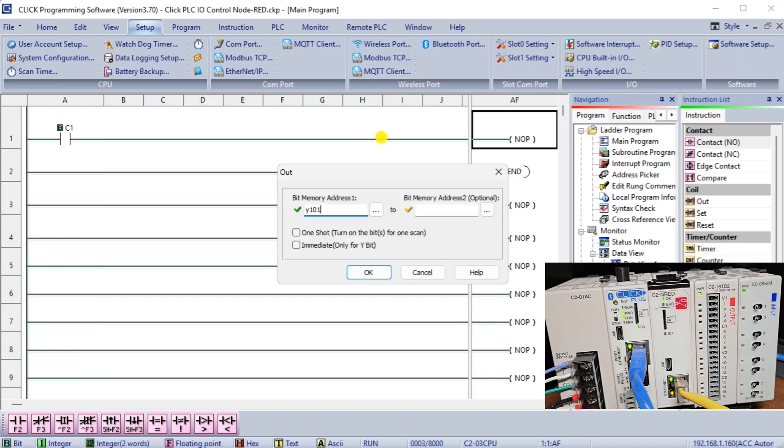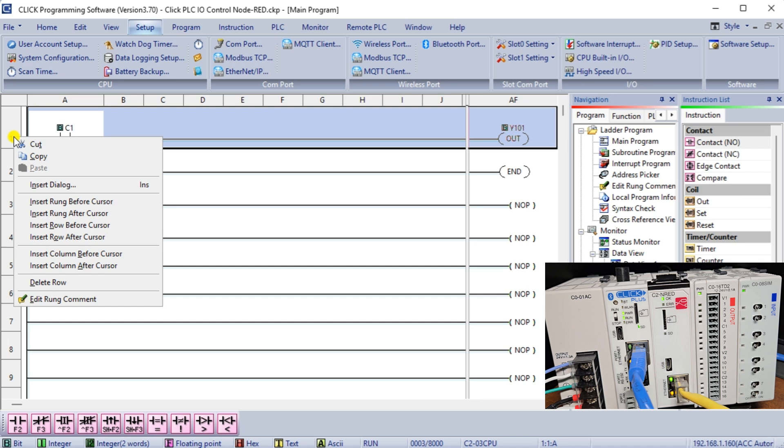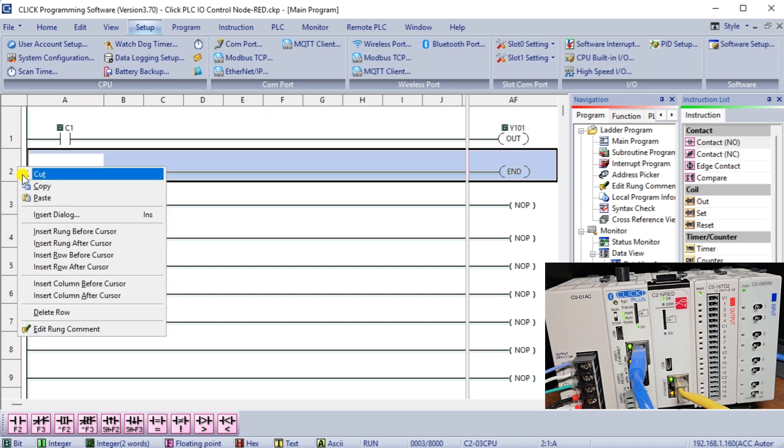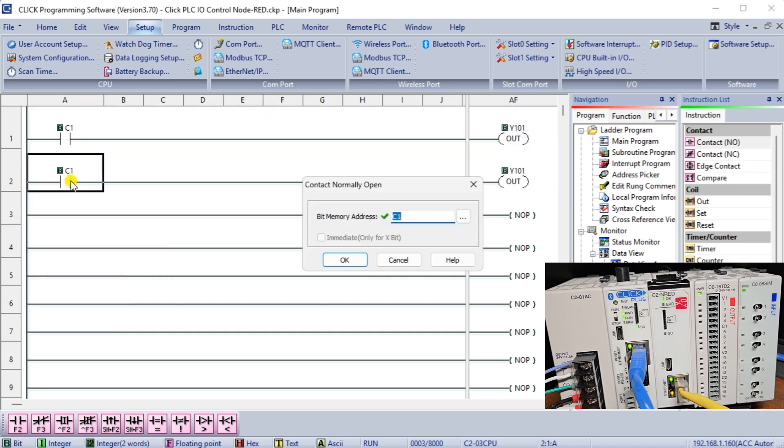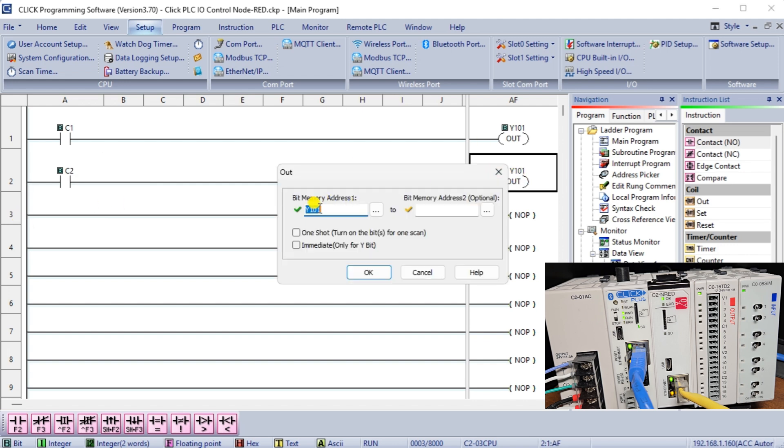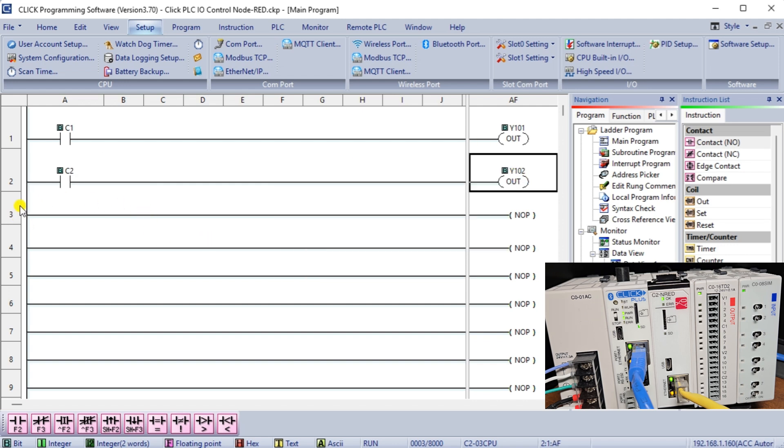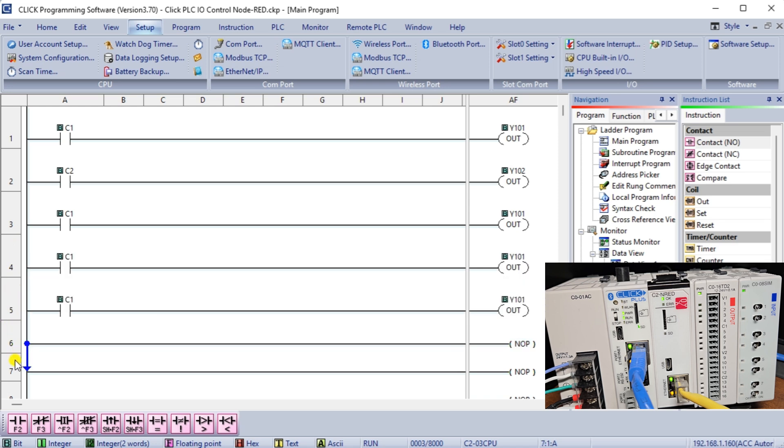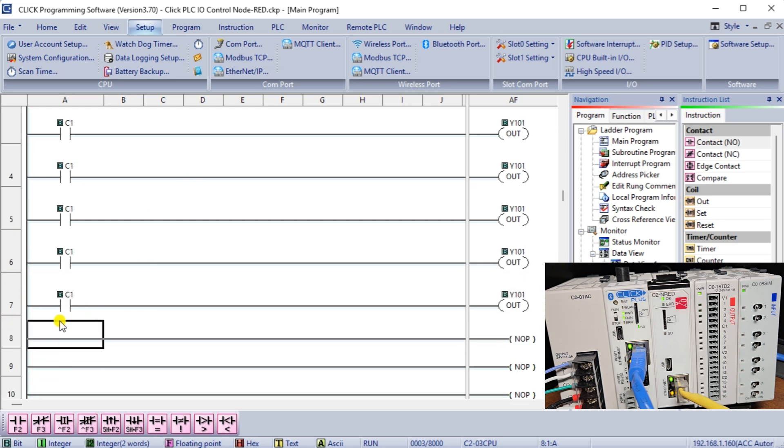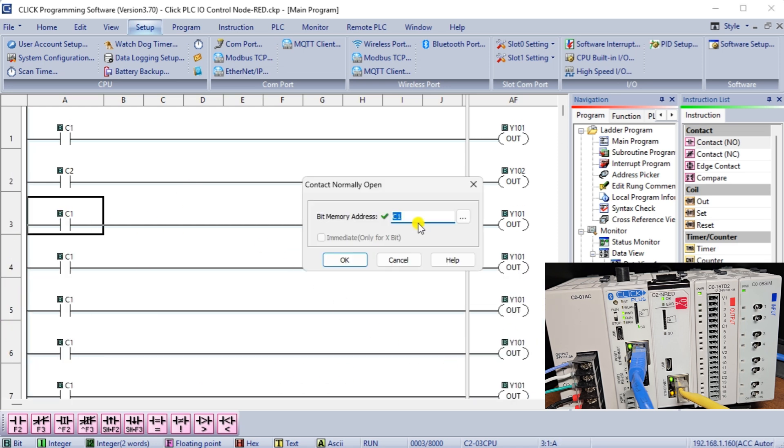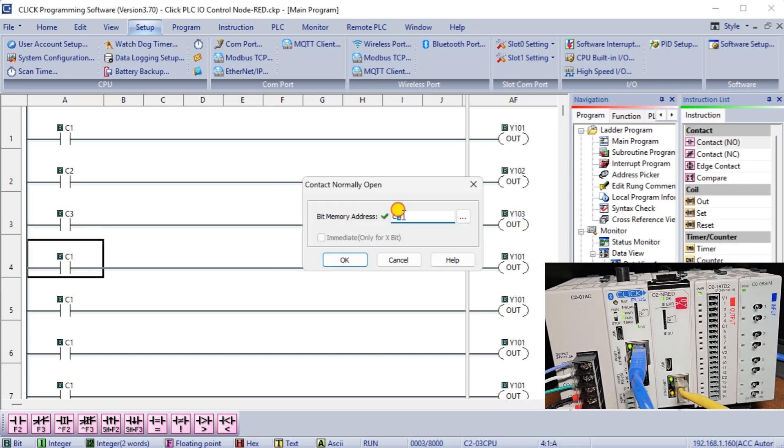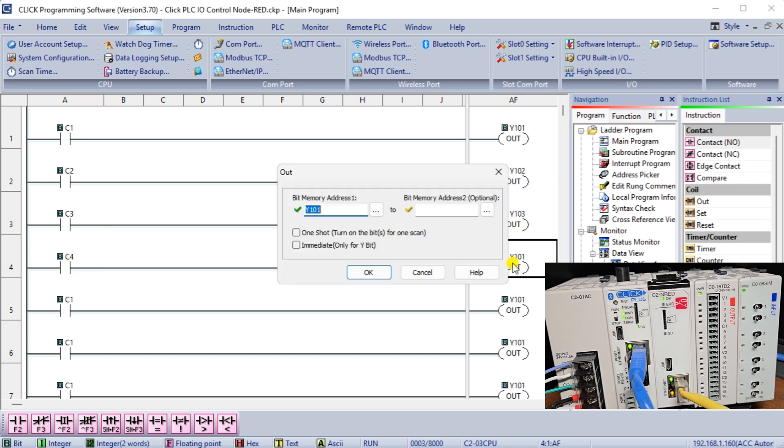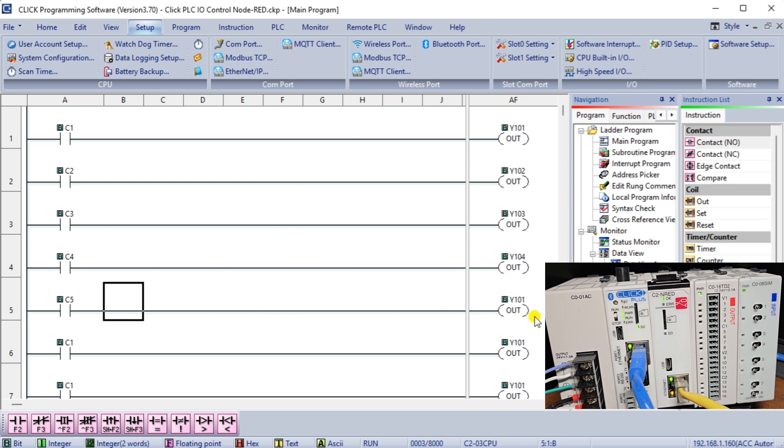In this context, it is essential to note that any control actions using the flow program should focus exclusively on manipulating internal memory areas. These internal memory areas such as C1 to C8 should be utilized to control the PLC outputs indirectly. By incorporating these controls in parallel with your conditions on a rung, you can effectively regulate the physical outputs of the PLC while maintaining a systematic and organized approach to programming.